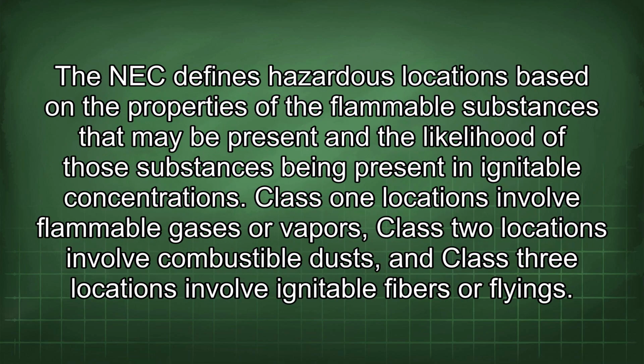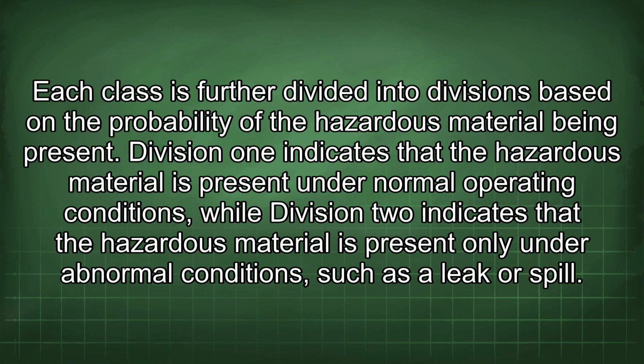The NEC defines hazardous locations based on the properties of the flammable substances that may be present and the likelihood of those substances being present in ignitable concentrations. Class 1 locations involve flammable gases or vapors, Class 2 locations involve combustible dusts, and Class 3 locations involve ignitable fibers or flyings. Each class is further divided into divisions based on the probability of a hazardous material being present. Division 1 indicates that the hazardous material is present under normal operating conditions, while Division 2 indicates that the hazardous material is present only under abnormal conditions, such as a leak or spill.